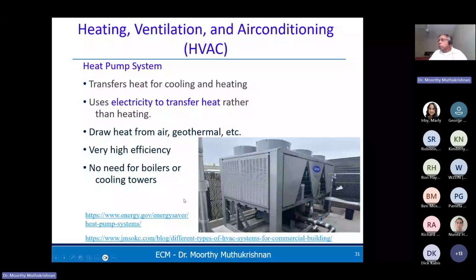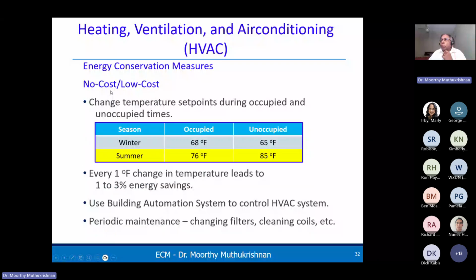All we have to do is just change the temperature. For example, during the winter, people want to set it at 70 degrees, maybe 72 degrees. It might be too high. So we can reduce the temperature to 68 degrees when the building is occupied. And when it is unoccupied, for example during the evening and nighttime hours, when nobody's in the building, why do we have to heat it to 68? So reduce it to 65, even below that. Again, it all depends on the particular client and building, but this is what we recommend.